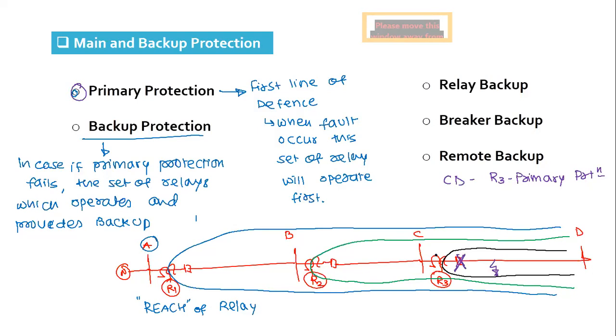Okay, by chance it happens in the system. Suppose here the circuit breaker is not tripped by relay R3. There are many reasons, we will discuss it later on, but this may happen because there is some error in the CT here and it has not given the correct current to the relay. Suppose the CT is okay, but relay R3 itself has some problem. There is some damage to relay R3 and it has not operated. Then also the breaker may not trip.